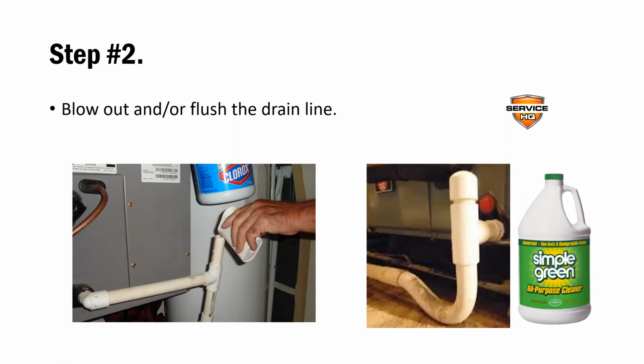Now, when it comes to blowing it out, you could wrap a rag around it and then physically blow on it, if you're brave enough. It can be gross, it can be dirty. Sometimes we'll do that, or if we came out to do your maintenance, we would either do that or we would use nitrogen. We keep bottles of nitrogen on our vehicles, and we'd use that to blow through the drain line.